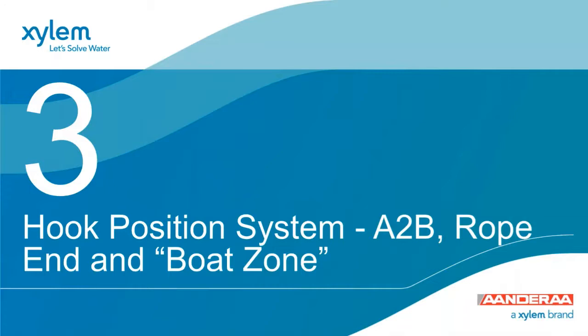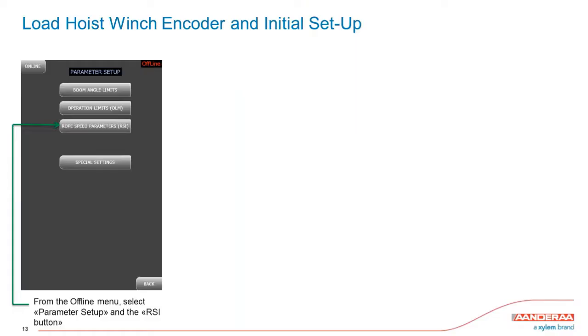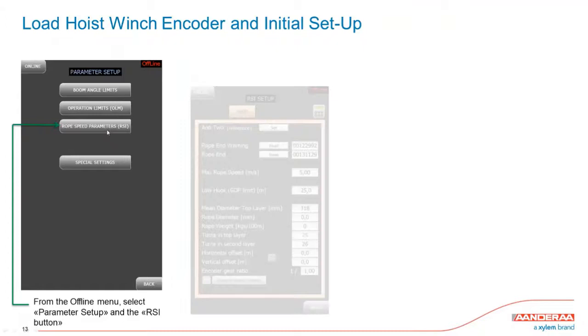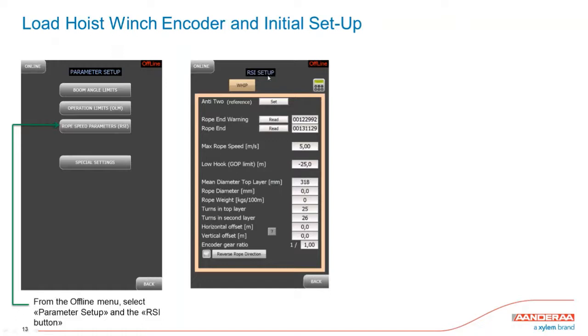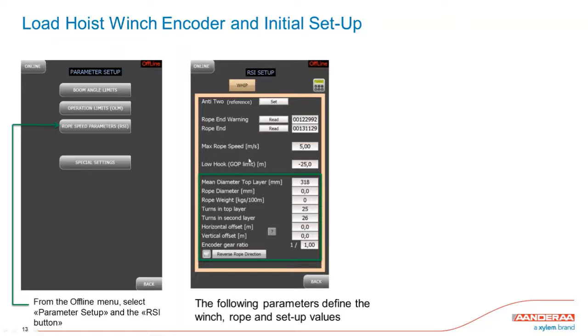We'll now go to the hook position system, which also sets up the A2B anti-two-block position, the rope end limit, and together with the OLM, defines a boat zone. Going offline, we go to Rope Speed Parameters RSI — more precisely, the hook position. Operating the push button takes us into the RSI setup. The setup is more comprehensive than the OLM, but again it is only done once and you can forget about it afterwards. All the numbers relate to defining the winch, the rope, and setup values.